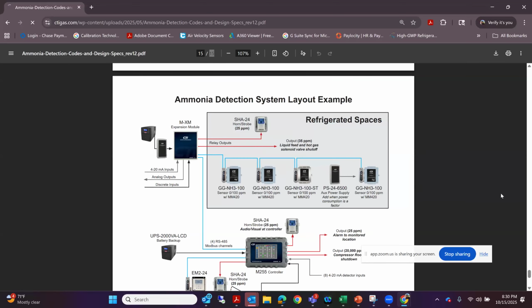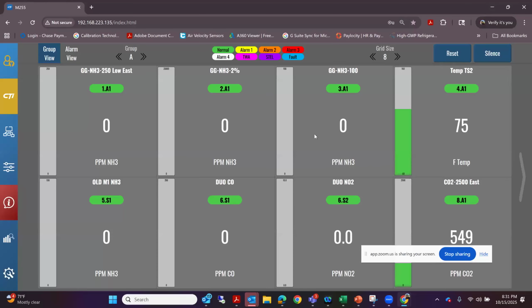Doing it this way really sets up the Modbus systems for future expansion. It sets them up for future gas detection. If there's another gas out there that you might need, or if you started doing CO2 on your dock, along with your ammonia sensors, you can come right off here and add the CO2 sensors because you decide you're going to do some dry ice. Or battery room sensors, going past the battery room, and you needed a hydrogen sensor in there. Well, you just come right off here and add your hydrogen sensor in there.